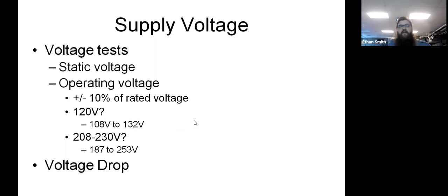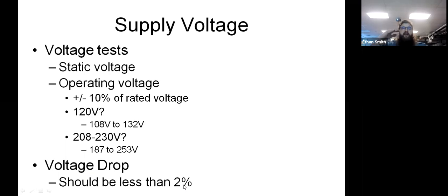Voltage drop is what we see when equipment is operating and experiences a voltage drop when it starts operating. So this is a voltage drop from your static voltage. So if you take your static voltage and it's at 115, your voltage drop should be less than 2% when it starts running. If it starts running and you drop more than 2% on your operating voltage, that means you have an electrical problem upstream of your unit. Okay, you've got loose connections, you've got undersized wire. All those things are going to generate heat and premature failures. So on that 120 volt circuit, your voltage drop should be less than, let's see, 3 volts once that thing kicks on.